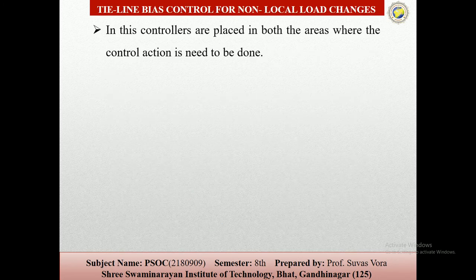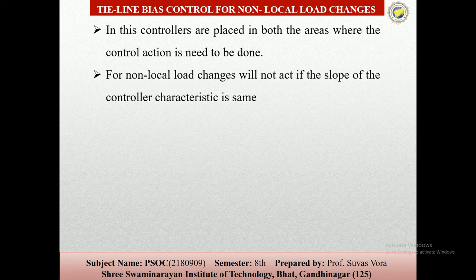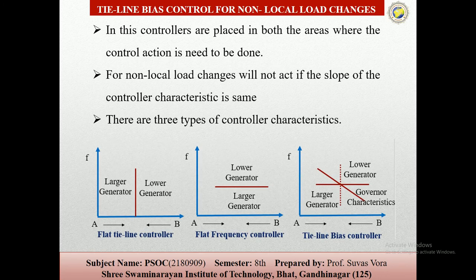Now the non-local load changes. In these, controllers are placed in both the areas where the control action is needed, and the non-local load changes will not act if the slope of the controller characteristic is the same. There are three types of control characteristics: flat tie line controllers, flat frequency controllers, and tie line bias controllers. The tie line bias system is connected for universal and non-local changes.